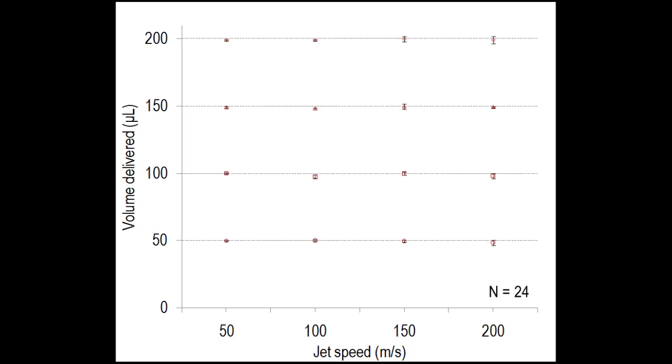This gives us a tremendous amount of control depending on how much current we put in. As you can see here, we can successfully deliver a wide variety of volumes of drug at a wide variety of velocities with a very low degree of error, something a needle can't do.